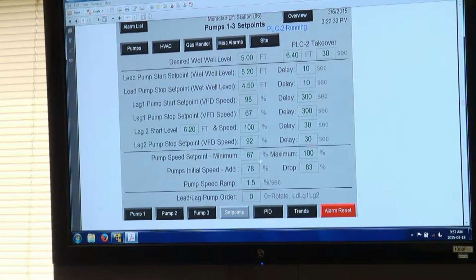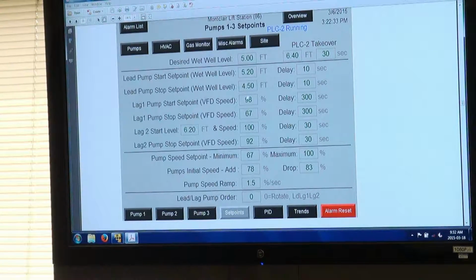67 is your minimum. This is protected at the VFD at 40 Hertz, which is 66.6. I just make it easier. And your maximum's at 100. If you ever change your maximum, make sure it's greater than your second pump that's going to start. Otherwise, we're never going to call a second pump.